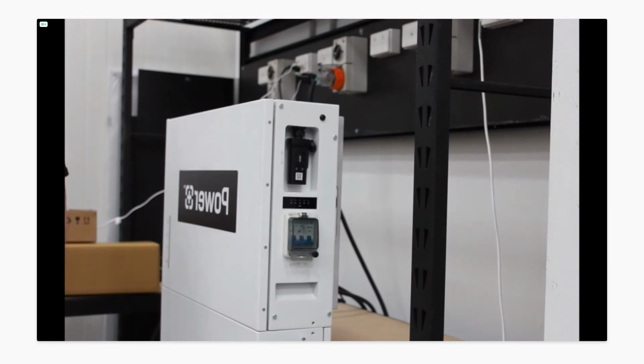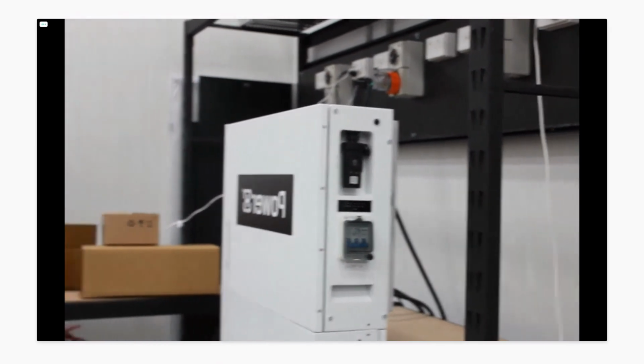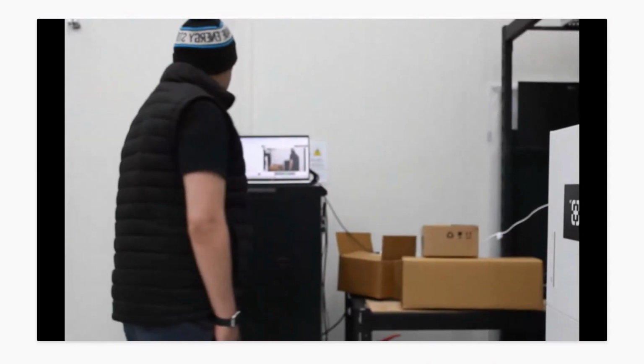If set up as a 3-phase, 3 units in parallel, will all 21 kilowatts be available? Yes, so 7 kilowatts per phase. If you have a load that is big enough to pull the 21 kilowatts, it'll all be available to you. The only thing we can't control is the balance of batteries between phases. So if phase 1 is very busy and phase 2 and 3 are not doing much, you can still pull that high load, but it's very likely in that backup scenario, phase 1 will drop off first, because the batteries aren't combined, so they're not sharing their resources in that scenario.